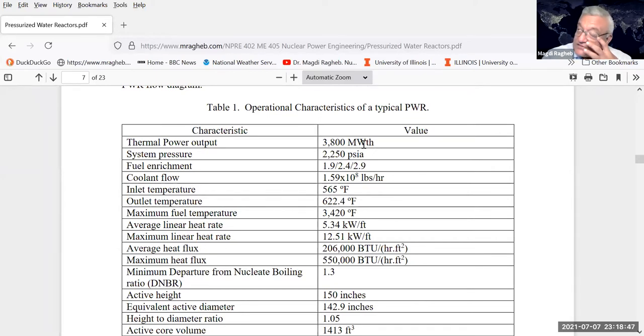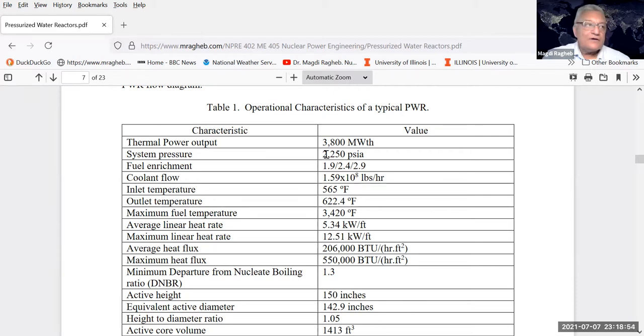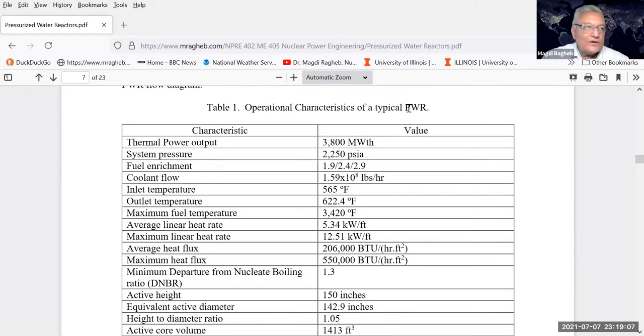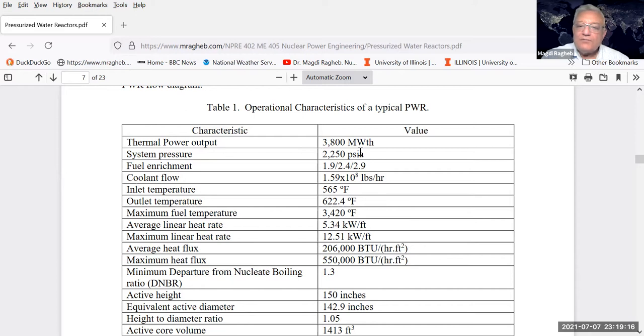As engineers, we cannot just use the rated power in megawatts without specifying whether it's electrical or thermal energy. The pressure for the coolant is high - pressurized to 2,250 pounds per square inch absolute (PSIA). The boiling water reactor, where we do not pressurize the water and allow it to boil inside the core, operates at almost half that pressure, about 1,000 pounds per square inch absolute.